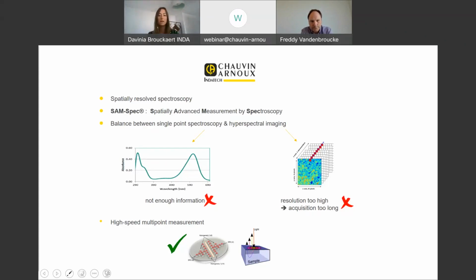So SRS can be considered as a simplified hyperspectral imaging system where fibers are linked to a two-dimensional CCD detector to collect the NIR signal from the inspected sample at discrete image pixels. So that allows to provide high-speed inline measurements in a variety of production environments and will be easier to integrate also than a hyperspectral imaging unit.